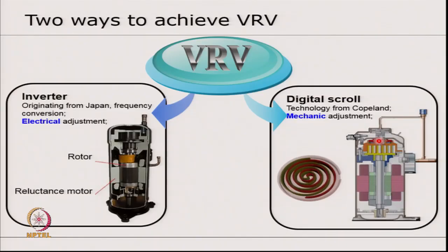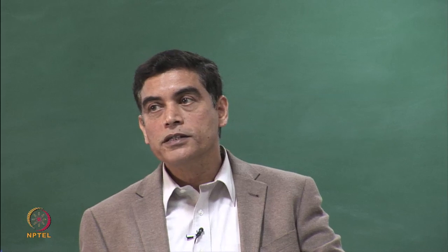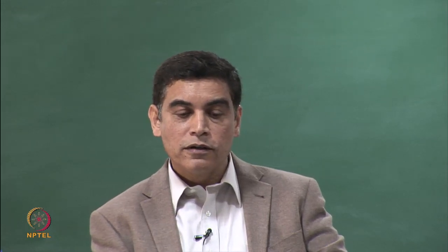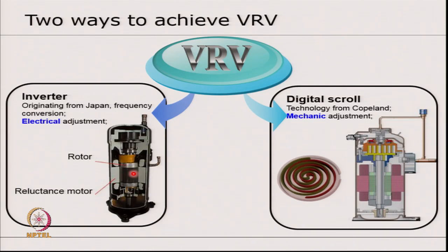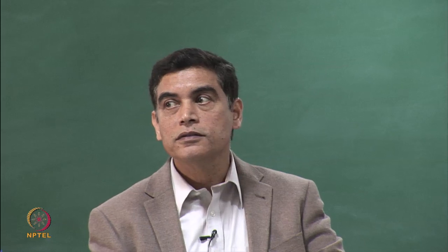So the digital scroll technology is from Emerson. Copeland is a brand of Emerson, and we touched upon how this is unloading. It is found to be effective if the part load does not go below 40% for a substantial period of time; then this seems to be giving some energy savings. But if you really want to go down to 30% of load, then a variable speed drive is the right solution. Here you have a DC motor, so the losses at low speeds are minimized. You could have a much higher part load efficiency with a DC motor than you could have with an AC motor.